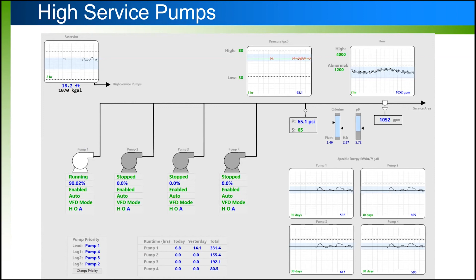You also have set points to set your high set point and your abnormal set point for your flow rates, right? So here we have the high service flow rate. We're showing pressure and a pressure set point here where you can change it, and also showing things like specific energy or energy consumption. So with a high service pump station, it could be something you can monitor. Most VFDs nowadays can give you the power consumption of a motor. And then you have a flow meter down the line, and you can combine that data either in the HMI or the PLC, and really take a look at specific energy, which is a great way to determine if your pumps are operating properly. There's an example of that.